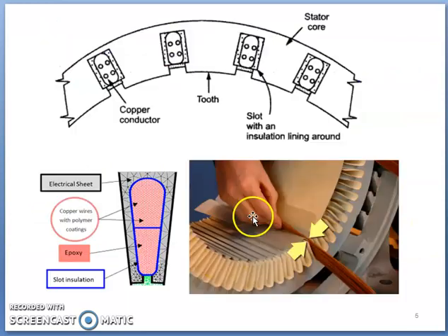Okay, if you observe these images here, depending upon output rating of machine, designer will decide the bunch of conductor to be put in the machine. It can be single turn or multi turn, or for large capacity machines, sometimes it may be bar type or strip type. Within this slot copper will be put, and to insulate conductors which operate at high voltage from ground potential, since stator will be at ground potential, insulation is put to insulate these conductors.